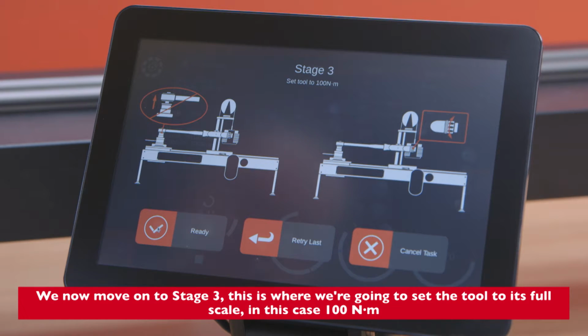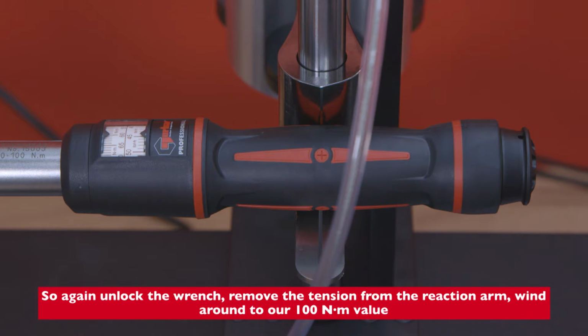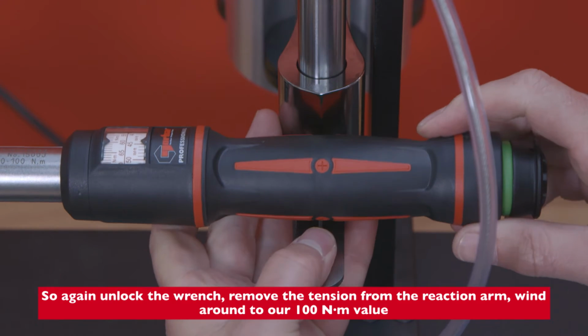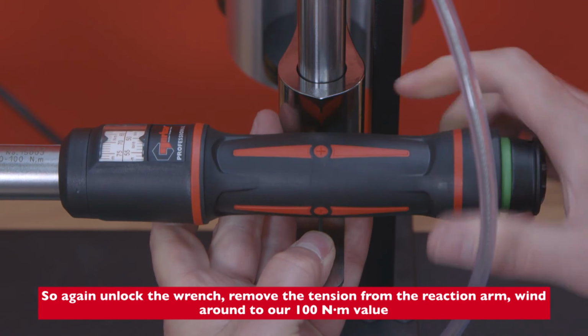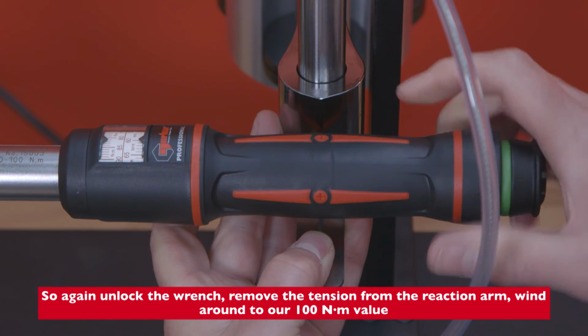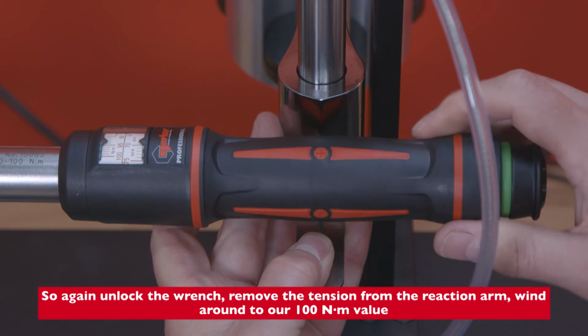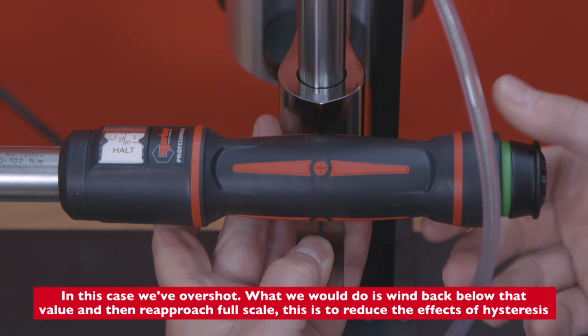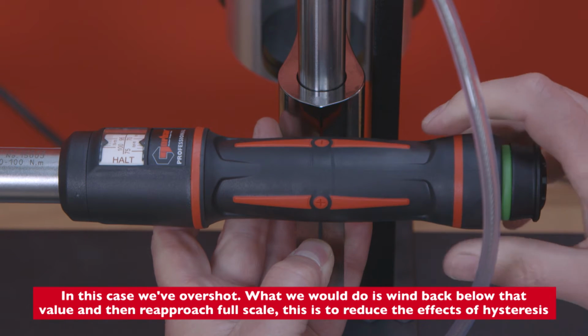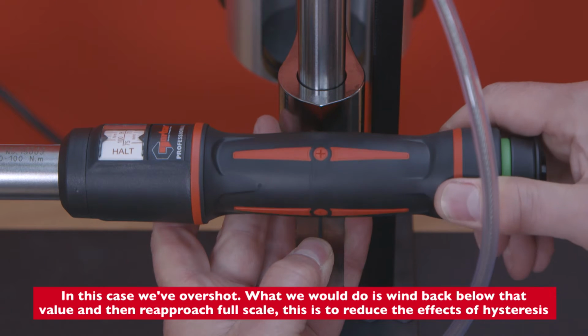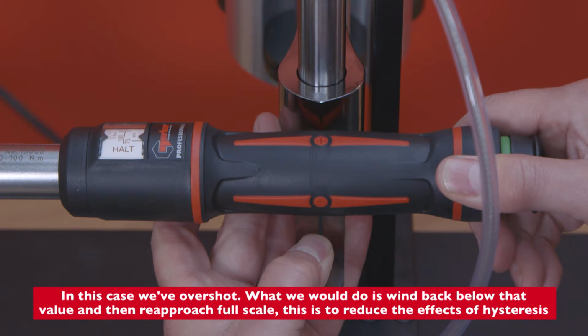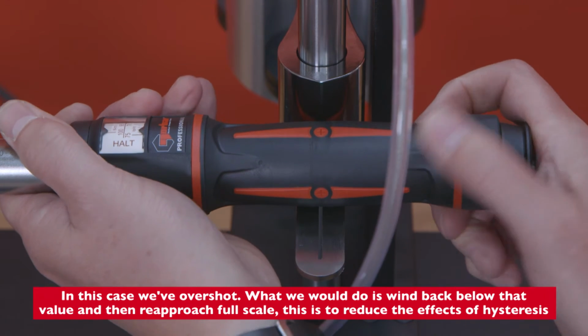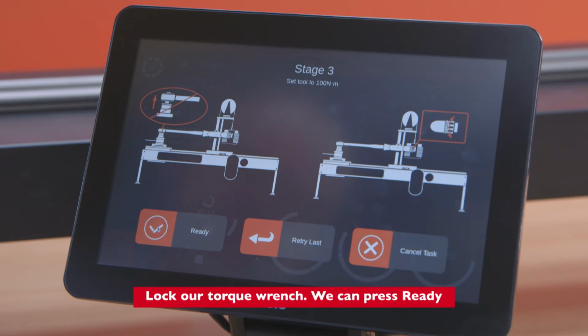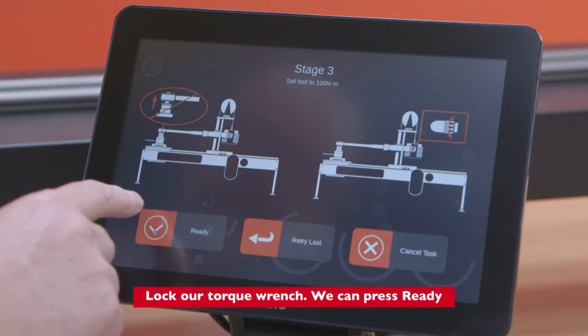We've now moved on to stage 3. This is where we're going to set the tool to its full scale, in this case 100 Newton meters. So again, unlock the wrench, remove the tension from the reaction arm, wind around to our 100 Newton meter value. In this case we've overshot. What we would do is wind back below that value and then reapproach full scale. This is to reduce the effects of hysteresis. Lock our torque wrench. We can press ready.